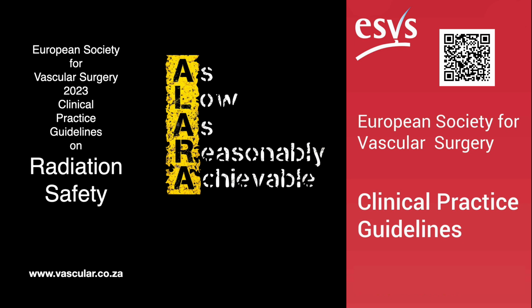Got it. Let's move to other radiation shielding equipment, things not worn directly. Right, equipment in the room. One option is suspended personal radiation protection systems. What are those? Like the Zero Gravity system? Exactly, that's a well-known example. These systems involve a ceiling-mounted boom suspending a large shield that covers the operator's entire body. It essentially replaces the lead apron, thyroid shield, maybe even shin guards.